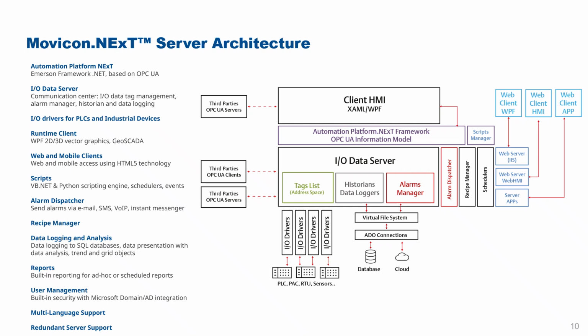Now the IO data server, that can also be redundant. So we do have this N+1 redundancy where you can have one or more backup computers. Two reasons for that. One is you might want better resilience than just having two computers with hot standby. So you can have hot standby +1 or +2 or more. The other idea there is that when you have clients, the clients are distributed across the available servers. So if you just had two computers with a lot of clients, if you have one failure, up to 50% of your clients suddenly transfer over to the backup server, and that could cause a big load on the system. So by having additional backup servers, that reduces that stress when a main computer goes down or is turned off for maintenance.